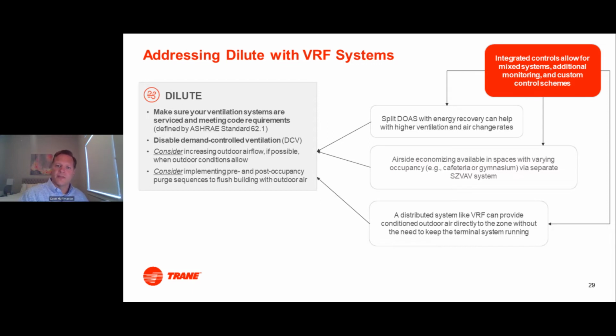Now, to achieve these dilution recommendations, again, you need controls that can really talk to your systems and your ventilation, whether that's a split DOAS with energy recovery, or a distributed system where you can actually duct your outside air directly to the space and make sure that you're providing that code ventilation at all times, or even a VRF system that maybe has a couple of units that aren't VRF. So an example here might be, let's say you have a cafeteria or gymnasium on a traditional rooftop VAV system, single zone VAV, something like that. You could have an airside economizer going for some of the systems like that. And then again, deliver code ventilation for your traditional VRF systems.